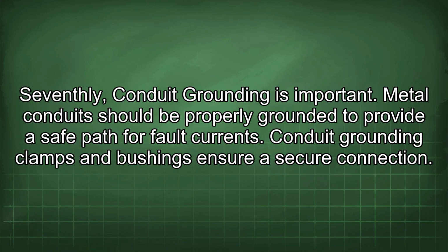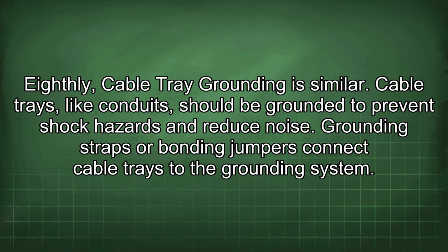Seventhly, conduit grounding is important. Metal conduit should be properly grounded to provide a safe path for fault currents. Conduit grounding clamps and bushings ensure a secure connection. Eighthly, cable tray grounding is similar. Cable trays, like conduits, should be grounded to prevent shock hazards and reduce noise. Grounding straps or bonding jumpers connect cable trays to the grounding system.